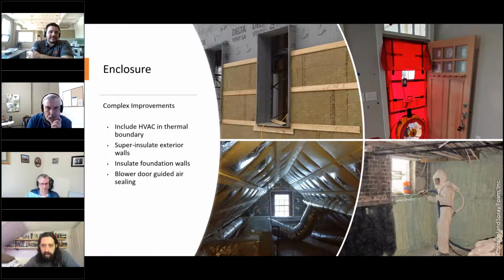So it's a cellulose hot roof that's, I don't know if this is 12 or 15 inches thick, but this is a hydro air system, I believe, in this attic, and you had exposed pipes, you had exposed ductwork, things outside the thermal boundary, and then they encapsulated over it, brought it into the thermal boundary, and something that can be done with spray foam can be done with cellulose as well.